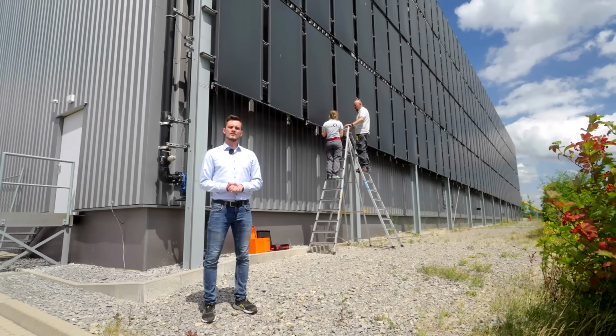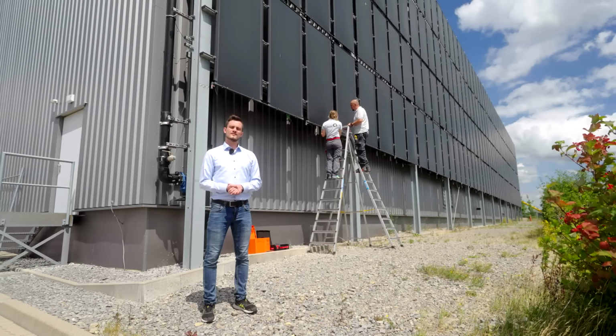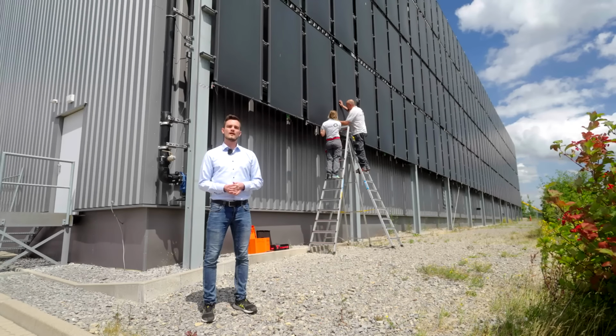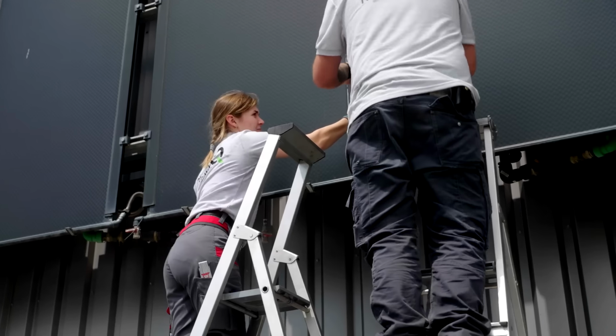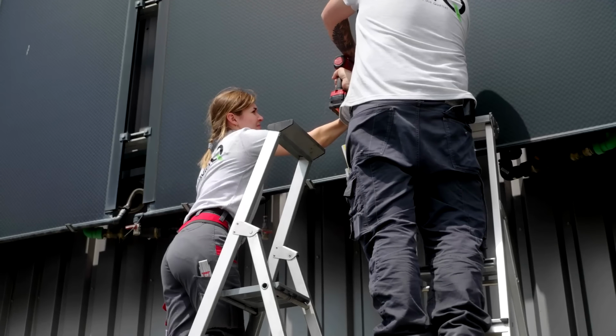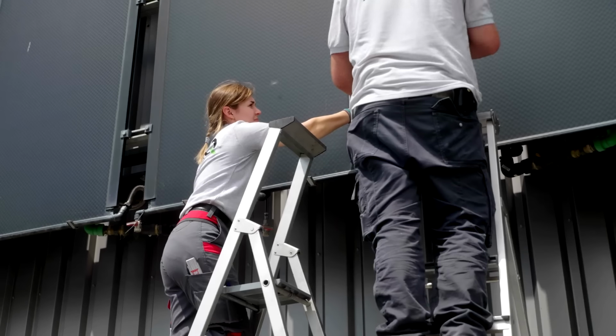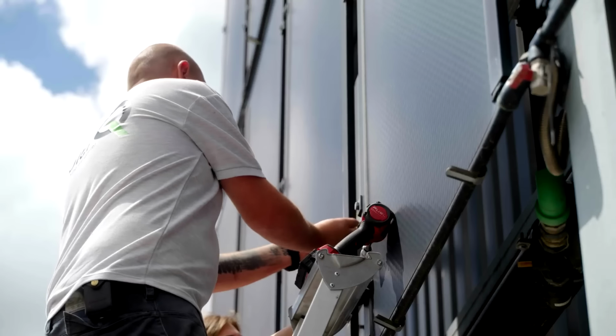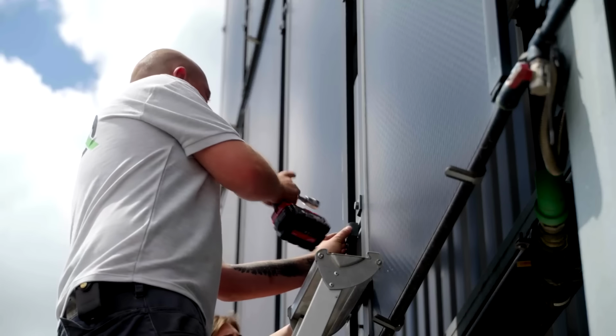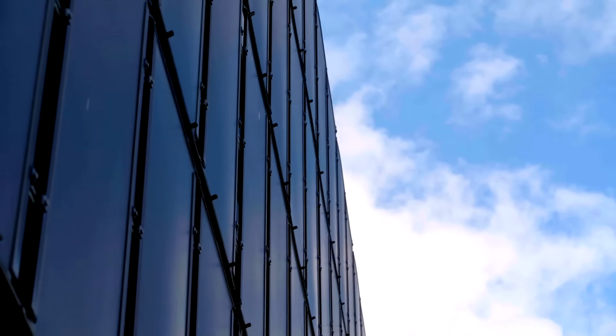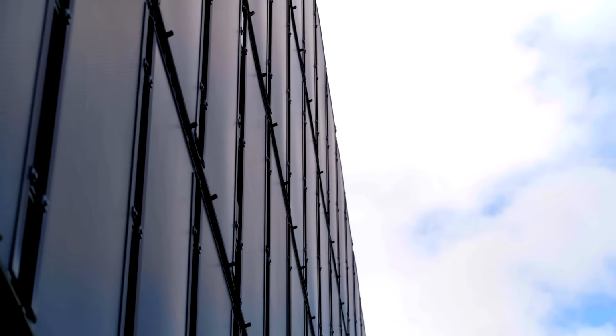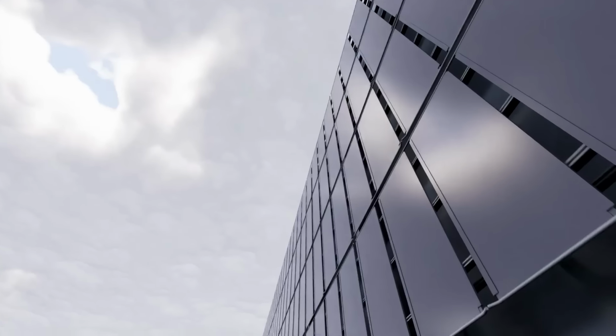These are solar collectors that serve two purposes. First and foremost, they capture solar energy to heat the brine. Secondly, they also function as solar air collectors that utilize ambient energy even when the sun isn't shining. These absorbers also contain a water glycol mixture. This allows these so-called multi-Q absorbers to function not only as solar absorbers, but also as air absorbers, literally absorbing warmth in the air. And this is how it works.